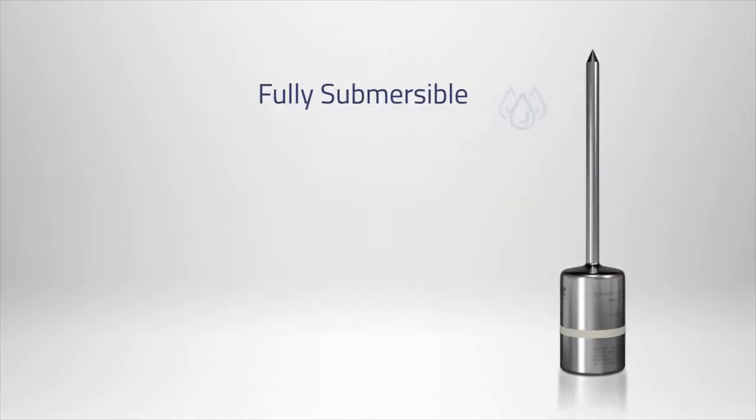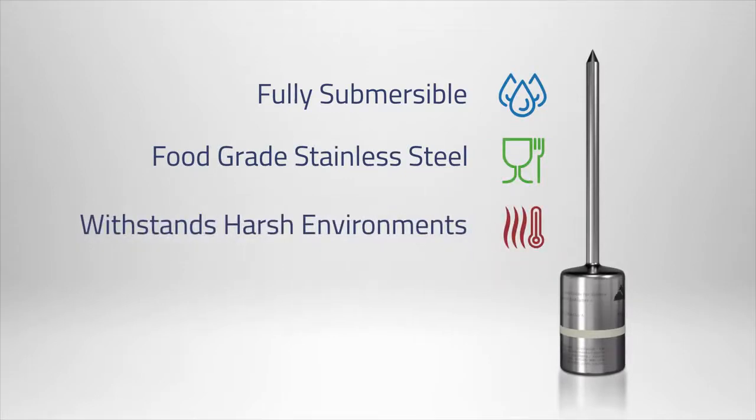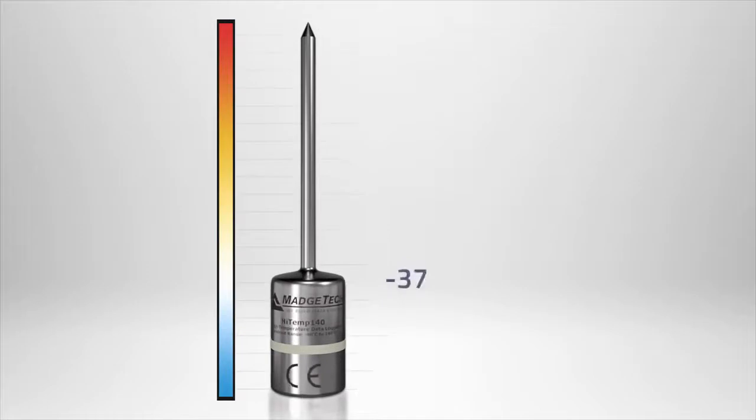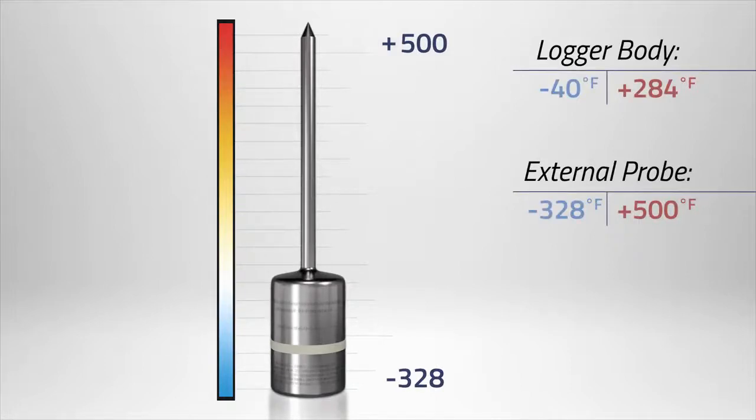The HITEMP 140 is a submersible stainless steel data logger designed to withstand high temperatures and harsh environments. The device can withstand temperatures from negative 40 to 284 degrees Fahrenheit, but the external probe is capable of monitoring temperatures up to 500 degrees Fahrenheit.